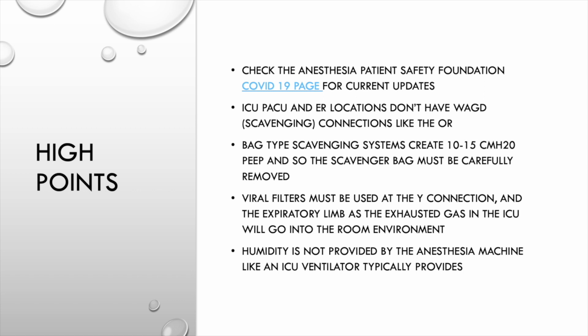Any of the bag type scavenging systems, when they don't have active suction applied to them, create about 10 to 15 centimeters of water pressure of PEEP. And that happens after about 30 to 45 seconds under normal circumstances. And so the scavenger bag must be carefully removed. This is counterintuitive to most clinical practice as anesthesia clinicians.